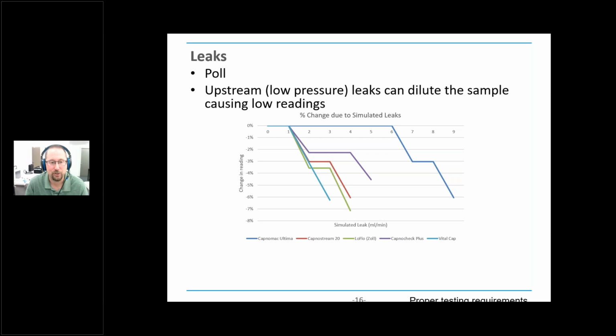So we actually introduced different size leaks into the system to see what the effect is. Again, every one of these devices will have a different flow rate, but even at just a 2 milliliter per minute leak, you're already starting to get off 2, 3, 4% almost in some cases. And by the time you get up to 3, 4 milliliters a minute, you're up past 6, 7% off.